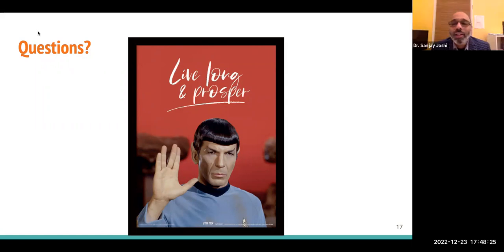Again, it depends. I can't speak about the specific components of your system, but this is where you need to put on your thinking cap and say, what can I take credit for? My recommendation is do the best to find a predicate device. It will make your submission go much easier, because you are telling the government that, hey, you already approved something like this before. Here is the name of the device, and look, my device is so similar.